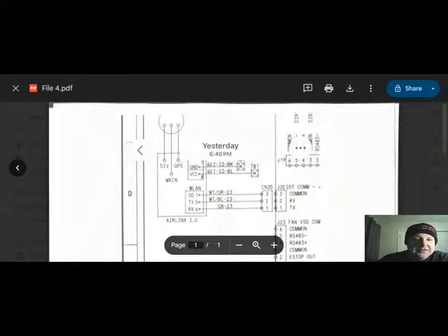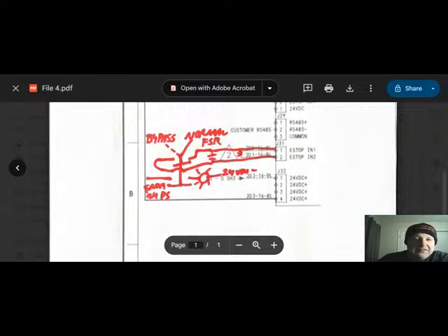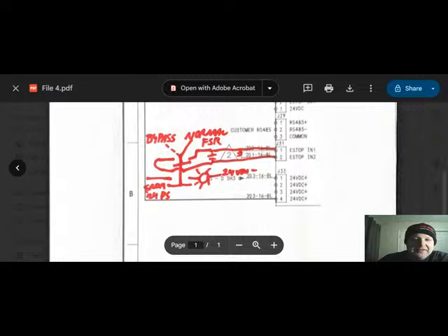Once again, we're going to put this 2-position switch in here. These are both going to be open when we're in normal. So we're relying on our fire suppression relay to latch this circuit. And when we switch this to bypass, this contact is going to make. Our circuit is now maintained by the manual switch. And then this circuit is going to make.